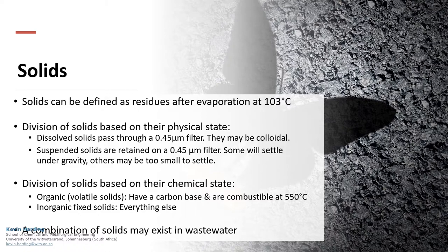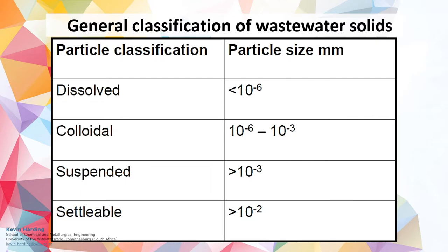Solids are anything that is left over after evaporation at 103 degrees Celsius. These can be dissolved or suspended solids, organic or inorganic. Solids that are smaller than 10⁻⁶ mm are classified as dissolved, while particles that are bigger are classified as colloidal or suspended. Those that are as large as 10⁻² mm are classified as settlable.